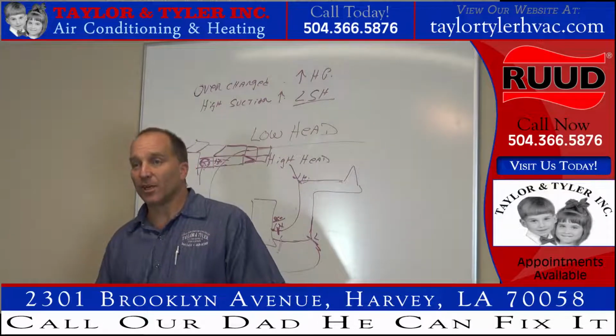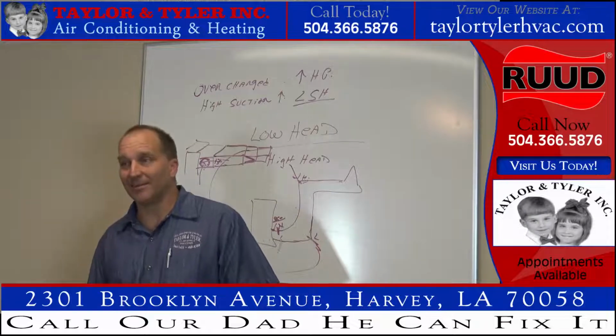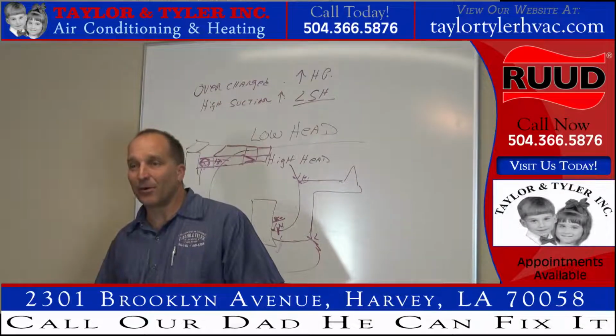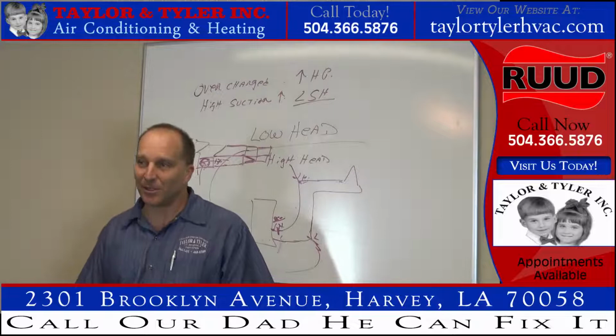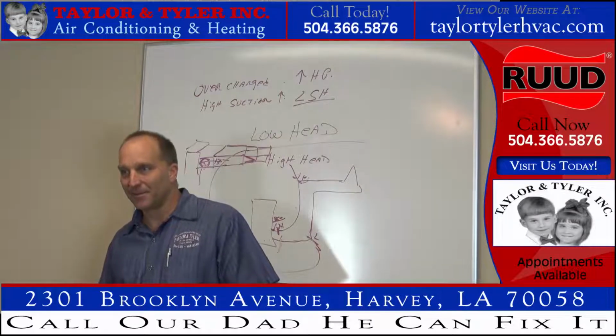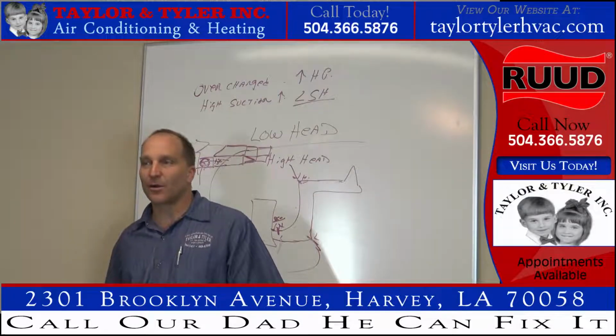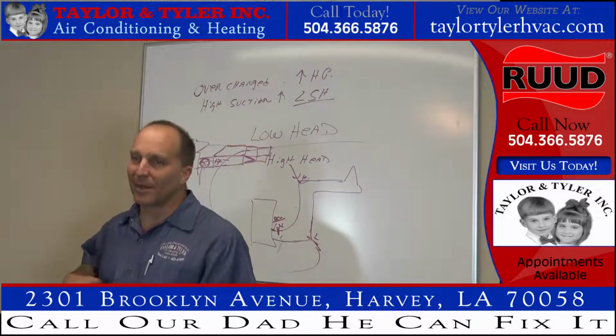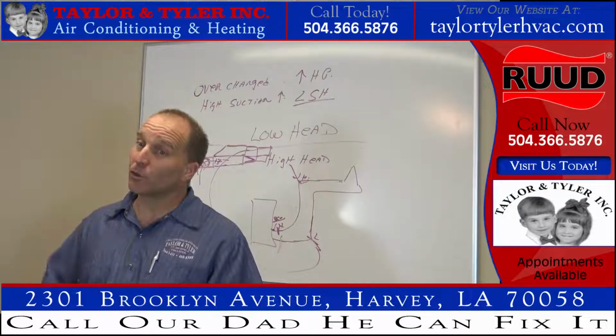You're going to feel your suction line, and your suction line is going to be hot. You're running a gas furnace over it, putting 100,000 BTUs into it. It's going to be hot. So you'll be able to feel that suction line on the outside. You will be able to tell that that's your problem by checking your superheat.